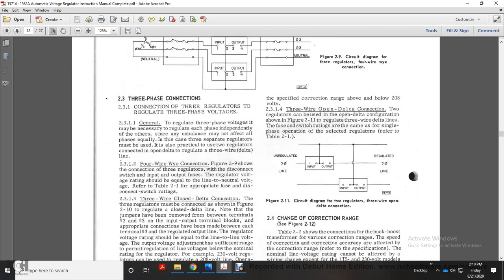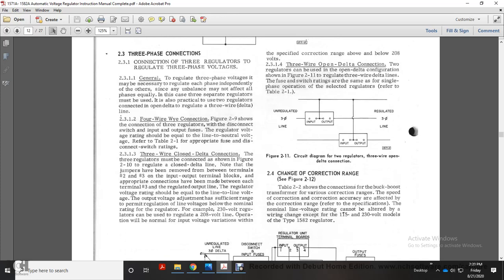3-phase connections. Connect a 3-phase regulator with the 3-phase voltage. It is general to regulate 3-phase voltage with each phase regulated independently, necessary because of the unbalance of the phases. But in the case of the 3 separate regulators must be used. It's also practical to use 2 regulators connected with an open delta to regulate a 3-wire delta line. Four-wire Wye connection. Figure 2.9 shows the connection with the 3 regulators with the disconnect switch. The input and output voltage rating of the regulator should equal the line to neutral voltage. Refer to Table 2.1 for the appropriate fuses and disconnect switch ratings.